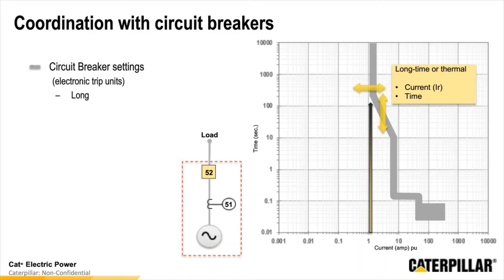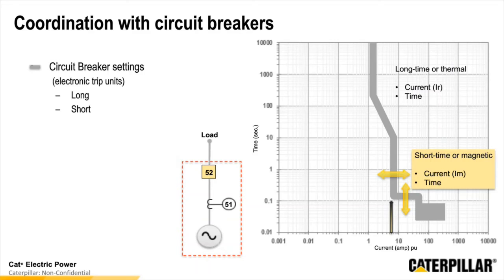So in this application, now we're showing that potentially we would be able to provide just over the fully rated current for just over 100 seconds, in the way that the system is designed. So the next part of this curve is the short time or the magnetic portion of the pickup. This again has a current and a time threshold that we can set. This looks a lot more like that definite time setting that we talked about before. So instead of having more of a curve, it's more of a corner function. And so we set the amount of current that we expect to see, and we have a time setting, and once we hit the current at that time, it will open the breaker.